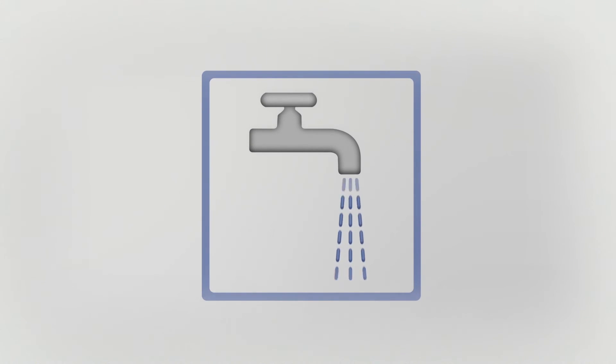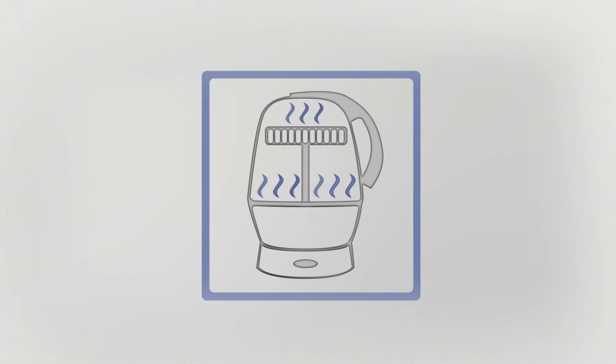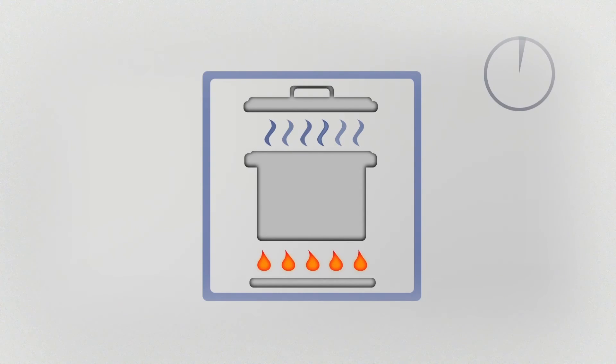The nebulizer should be disinfected once a week. A thermal disinfector can be used, such as a baby bottle disinfector. If preferred, the component parts of the nebulizer can be boiled for 5 minutes, and then left to dry.